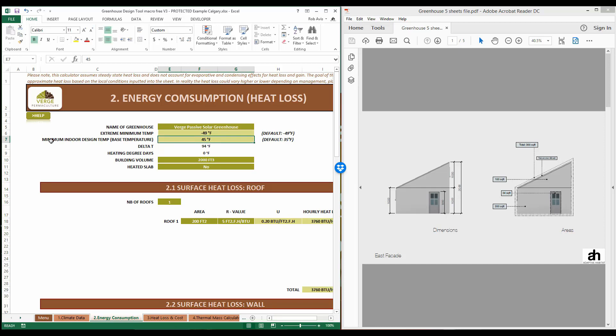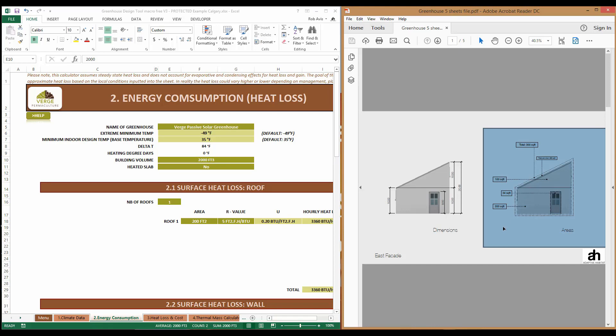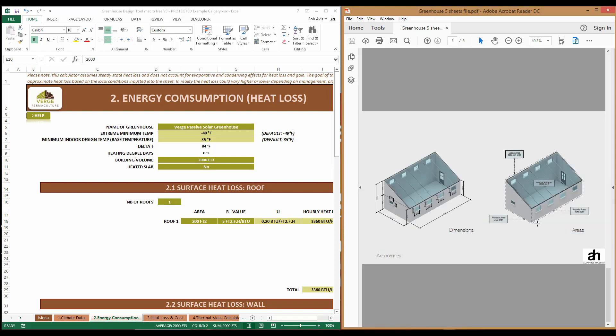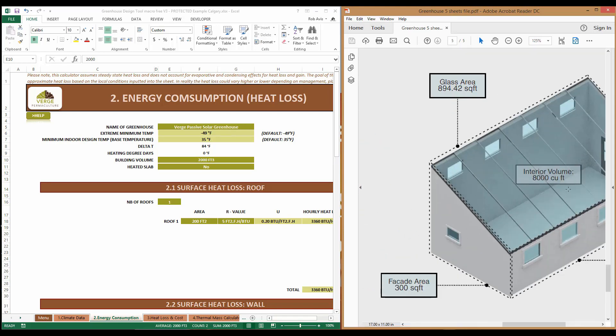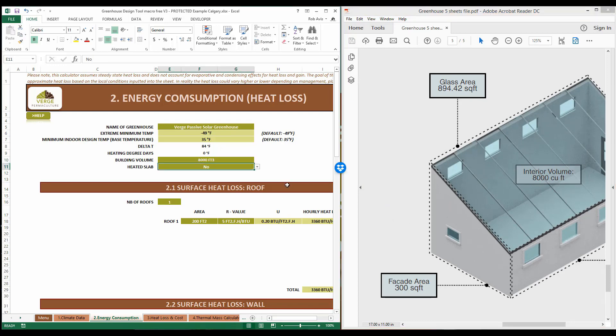Notice the default number is populated from the climate sheet that we just entered. We also need to enter the minimum indoor design temperature or base temperature. The temperature is easily accessible here and it is 35 degrees Fahrenheit. The next piece of information we need is the interior volume of the greenhouse. In our illustration, this greenhouse had an interior volume of 8,000 cubic feet. Next, the greenhouse calculator asks if we're going to have a heated slab, and I'm going to say no.